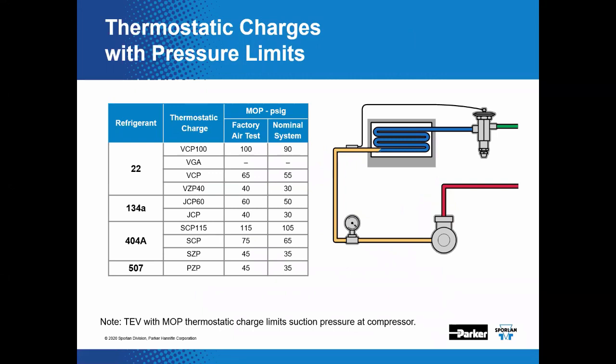Sporlan MOP — maximum operating pressure — charges limit the suction pressure returning to the compressor under high load, acting somewhat like a crankcase pressure regulator. This is beneficial on conventional single-compressor systems where additional horsepower is not available during high load situations. It is generally not required on most rack systems since another compressor can be brought online to lower suction pressure. The thermostatic bulb has a limited amount of liquid; under high suction temperatures the liquid eventually boils away, leaving only vapor, and the pressure in the bulb plateaus, ultimately limiting the suction pressure to the compressor.